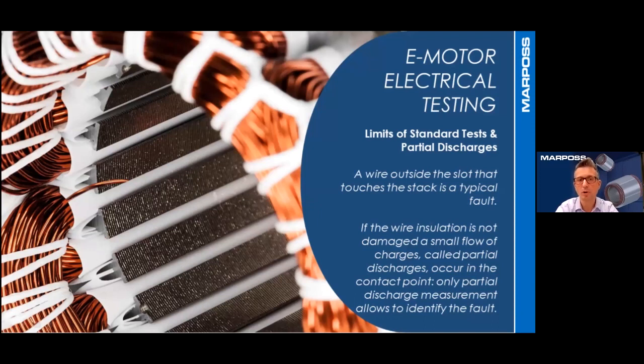This is an example of a typical fault that occurs when a wire outside the stator slot touches the stack. If the wire has the enamel scratched in the contact point with the stack, even the standard hipot test is able to identify the fault. But, as commonly happens, if the wire is well insulated, the voltage applied during the hipot test, even if quite high, could be not sufficient to break the remaining insulation material, and this fault cannot be identified. With the measurement of partial discharge carried out at the same time as the hipot test, 100% of these defects are always identified and filtered.